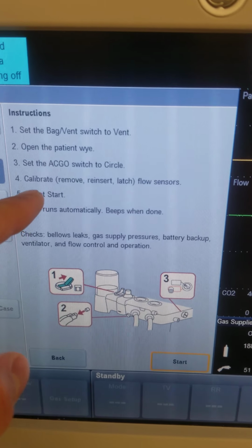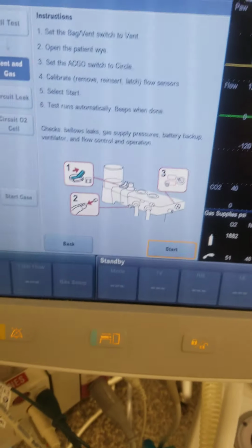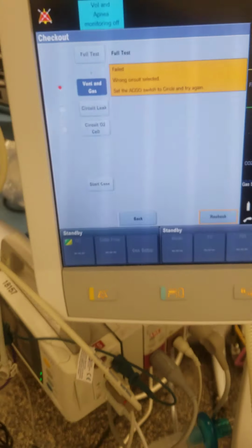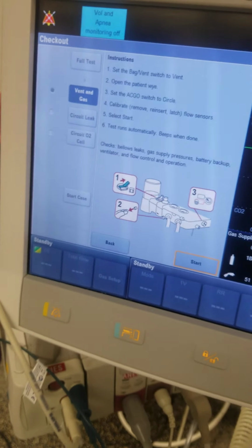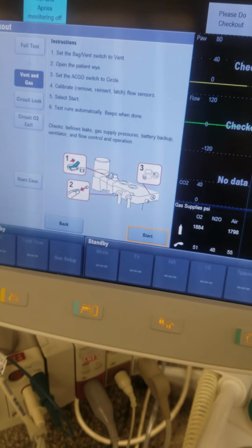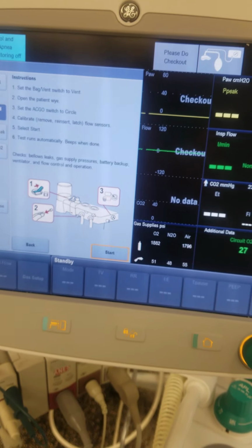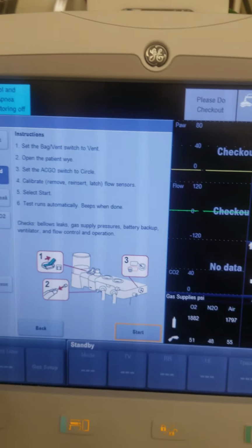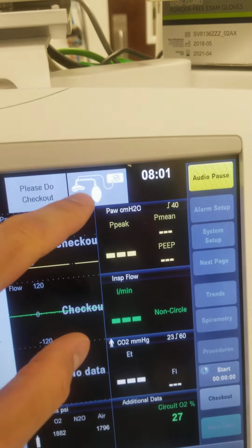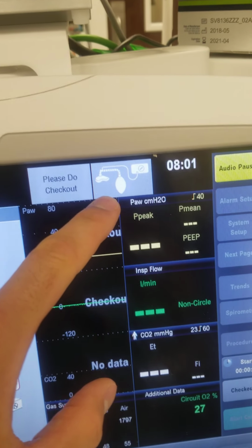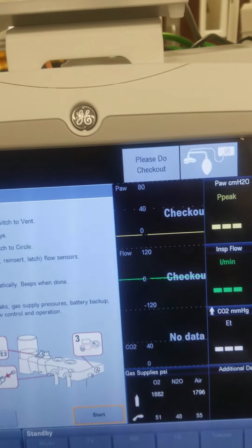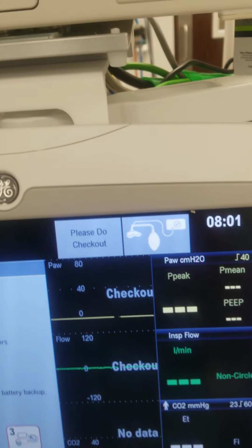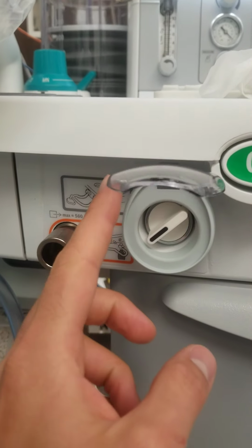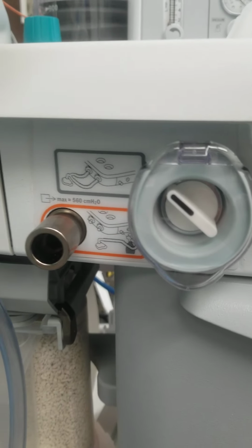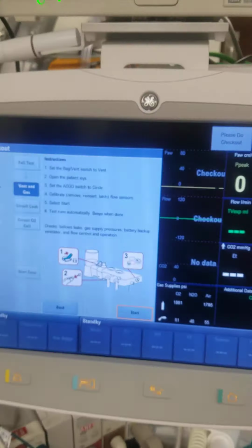So we calibrated our flow sensors, which was 4, and now we can start this vent check. So okay, let's see what we did wrong here. We did open patient Y. You know what we did? As I'm talking, you notice the symbol up here. This symbol says that we've bypassed that circuit, right? And we did that for a low P leak test. So it won't let you do the checkout because the right circuit is not selected. So we forgot to turn our common gas outlet down here, and this switch, we forgot to turn this back up. That was the problem. So now we can hit start.